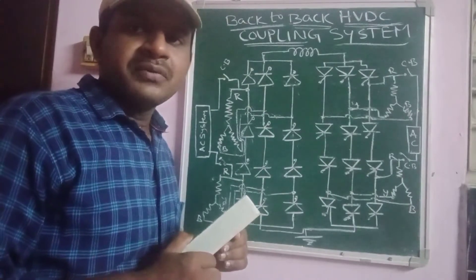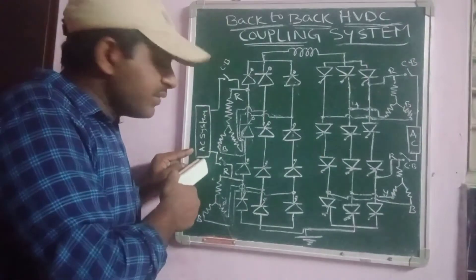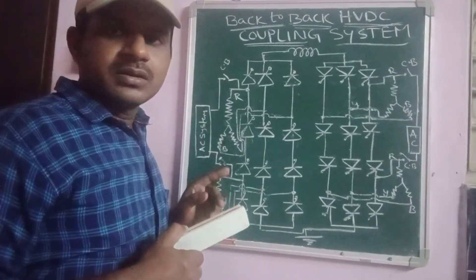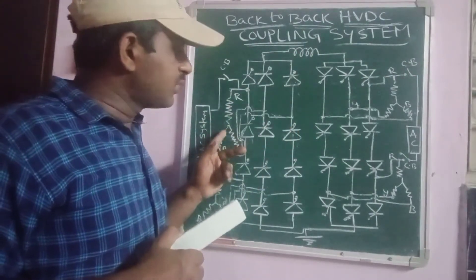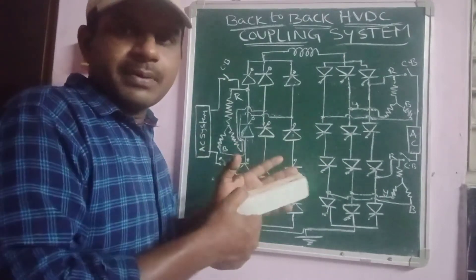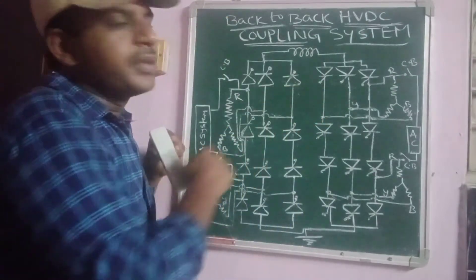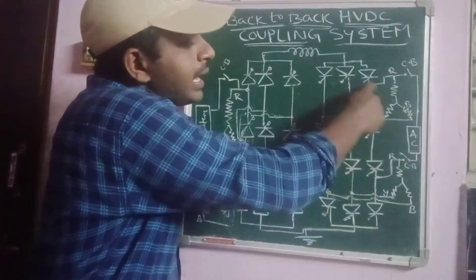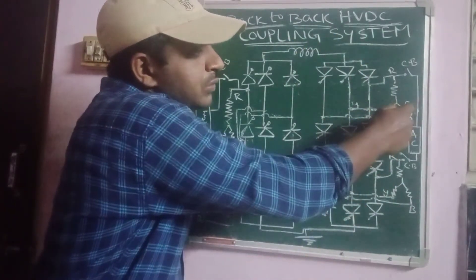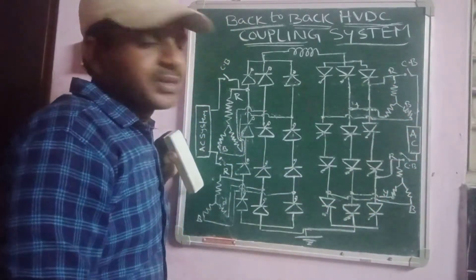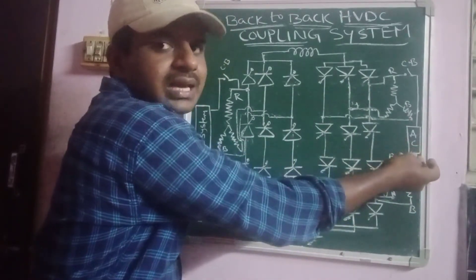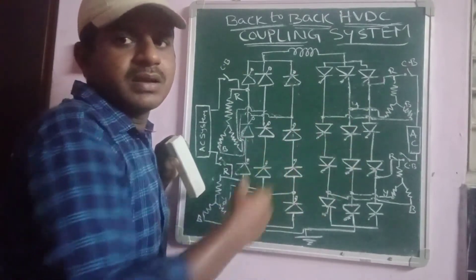The power conversion process works as follows: we supply AC power from conventional sources, which is fed into a transformer to step up the voltage. That voltage is given to the rectifier station, which converts AC power into DC power. The DC power travels through the entire DC link and is given to the inverter station, which converts DC power back into AC power. That AC power is given to two three-phase transformers, which step up the voltage again before supplying it to load centers, also called the grid.